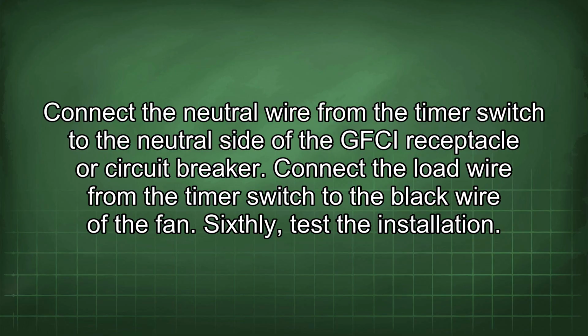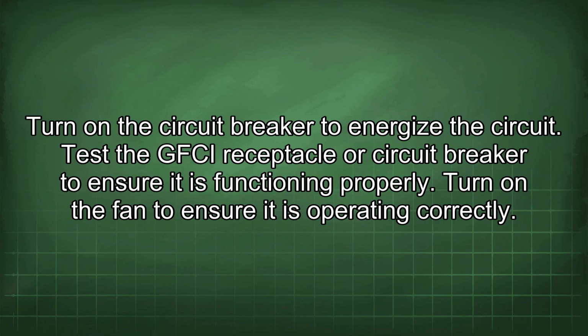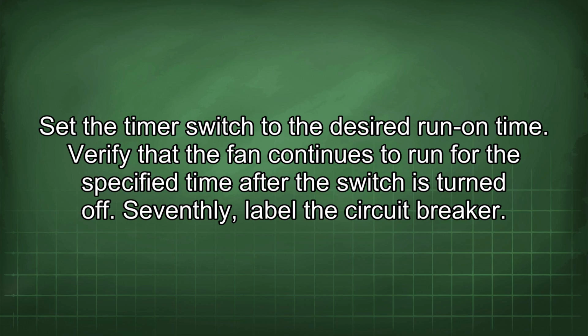Sixthly, test the installation. Turn on the circuit breaker to energize the circuit. Test the GFCI receptacle or circuit breaker to ensure it is functioning properly. Turn on the fan to ensure it is operating correctly. Set the timer switch to the desired run-on time. Verify that the fan continues to run for the specified time after the switch is turned off.